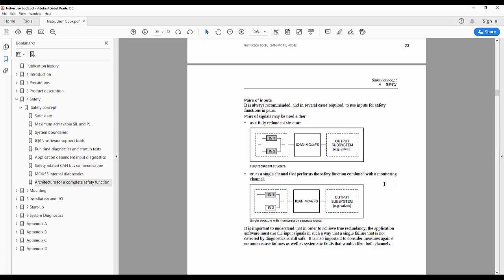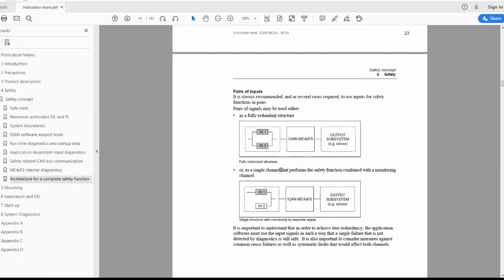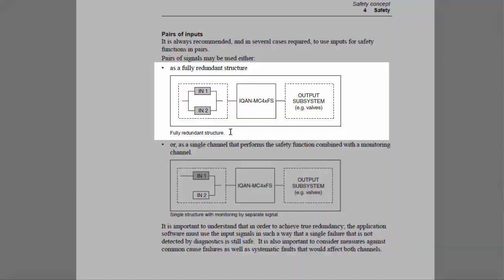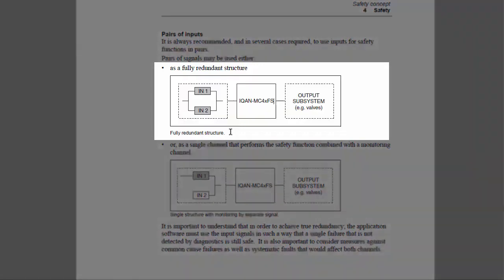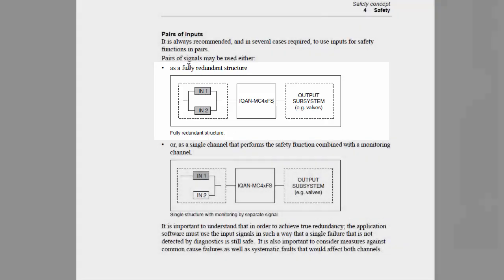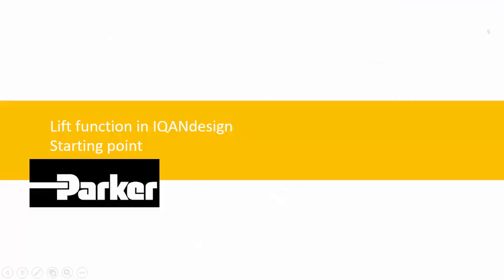There's really two ways to use this and I see a lot of people who use it as a single structure channel with just diagnostics, just using the second signal for comparison. But what I'd like to show here is how to combine the signals in a better way using both of the signals as a more redundant structure or as a full redundant structure where it doesn't matter if the diagnostics detects it, we're still going to get to the safe state and we're adding diagnostics to that. So let's see how that looks in IQANdesign.